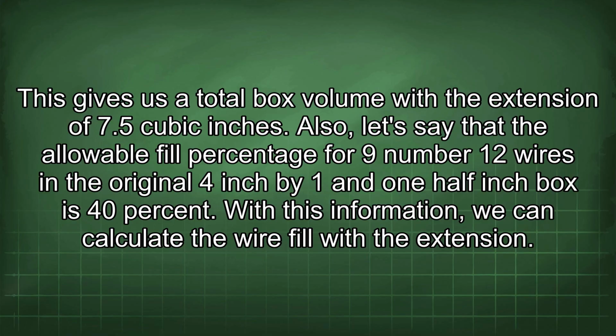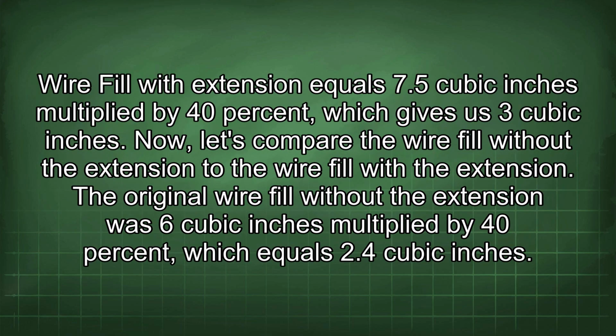Also, let's say that the allowable fill percentage for 9 number 12 wires in the original 4 inch by 1½ inch box is 40%. With this information, we can calculate the wire fill with the extension. Wire fill with extension equals 7.5 cubic inches multiplied by 40%, which gives us 3 cubic inches.